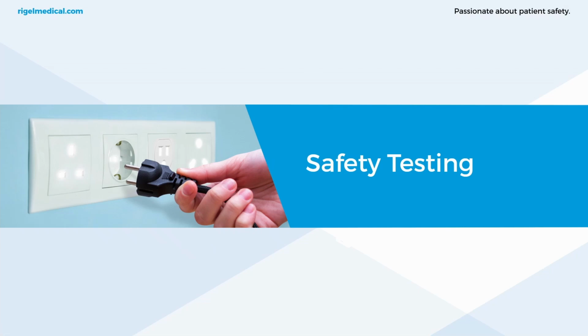So electrical safety testing, we know it's important, and it's a practice that should not be compromised. It just guarantees the safeguarding of clinicians, patients, and any visitors. The primary process is to prevent any patient or operator being exposed to currents that are not part of the functional operation of the device. These currents you will know as leakage currents, and I'll elaborate a little bit more on that in this section.